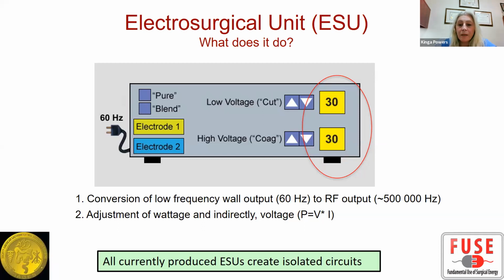And just remember that concept, that the power that you set depends on the volts times current. So for the same power, if you increase the voltage and decrease the current, you'll have the same power, or vice versa. The third thing that the ESU does is that you can set the mode, how the current comes out of the generator. The terms coag, cut, or blend determine the duty cycle, or how the current comes out, and I'll talk about that in a little bit. Just remember that for the same power, with high voltage and low intermittent current, you can have the same power with low voltage and continuous current. And that's called the duty cycle.